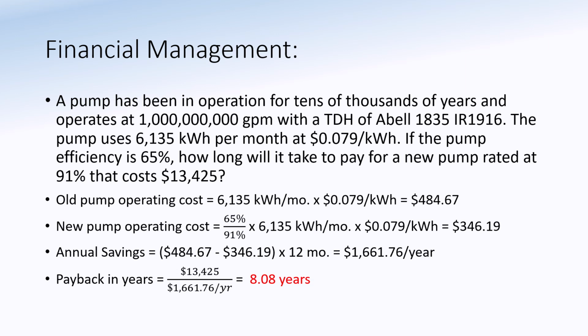We said, hey, this pump's going to cost us $13,425. So if we divide that by the $1,661, we get 8.08 years. So that's your ROI, or your return on investment.